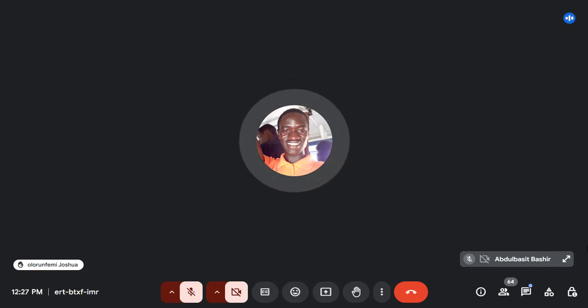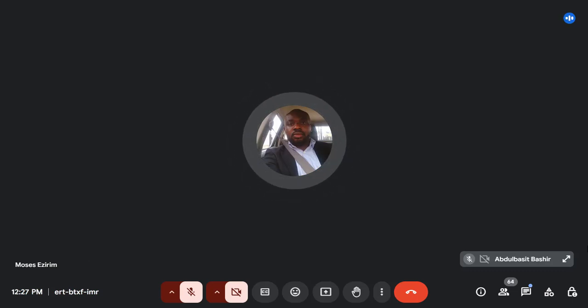So this is it for C&I. I said for C&I, you don't go to the facility and be writing. The reason why you don't go there and be writing is simply because all equipment are not operating at the same time. By you writing it, that there is what we call connected loads. You understand? By you writing it down, what you are noting down is the connected load.